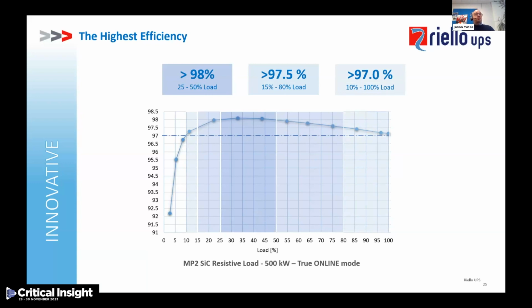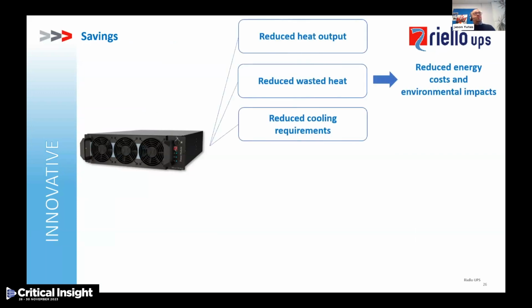Going further afield again, between the load levels of 10 to 100%, we are pushing efficiency levels up to and above 97%. And again, the beauty of this is when the UPS system is in true online mode. This is not an average efficiency figure. So we can say what savings can actually be made by using silicon carbide. Well, as we know, reduced heat output means reduced wasted heat, means reduced cooling requirements. That basically reduces overall energy costs and obviously the subsequent environmental impacts that come along with that.